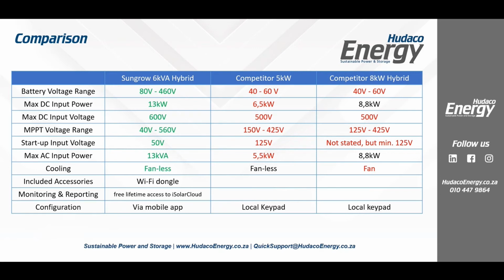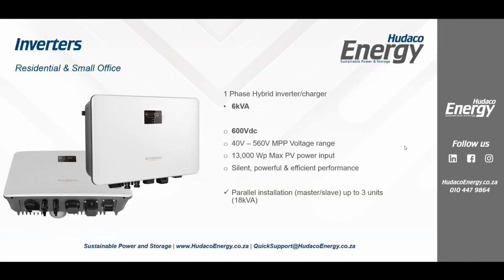The big cost, in fact, is in the batteries, but because we're getting 6,000 cycles out of the battery, it's a huge number. If you look at some of the other local ones, 4,000 cycles, so they call it 10 years, but 4,000 cycles is not 10 years at 1.6 a day. It's a hell of a lot less than that. In our particular case, 1.6 cycles a day for 6,000 cycles to 100% DOD is 10 years. Okay, so it's a proper, real guarantee. Again, backed by a listed company, and Sungrow itself is the most bankable inverter company globally. It's their 4th year in a row that they've received 100% bankability rating. It's the only company ever to have done that in the PV space.